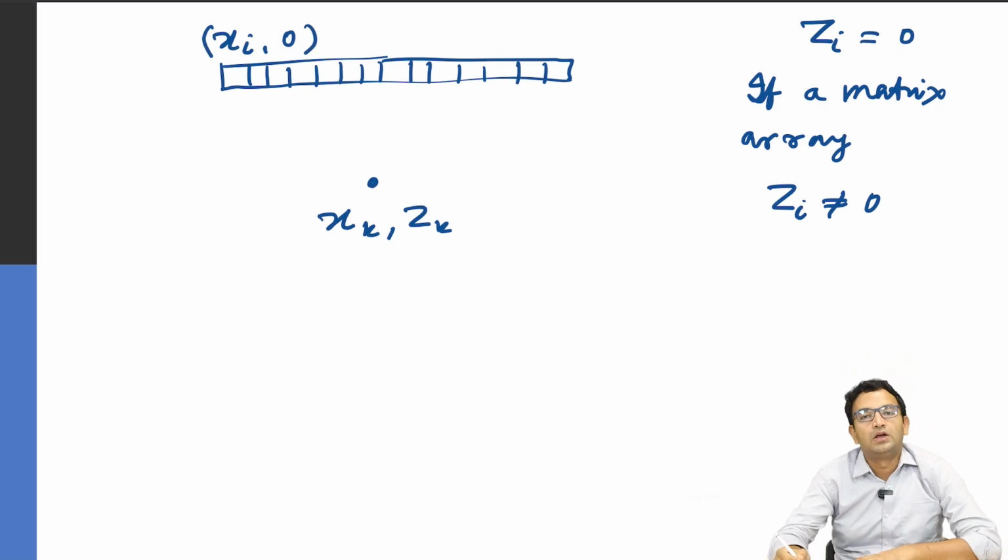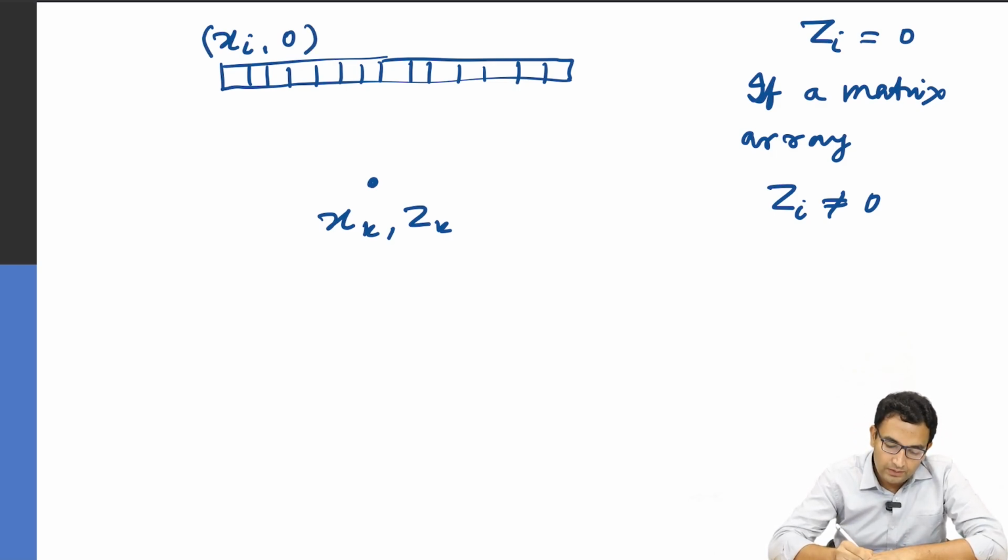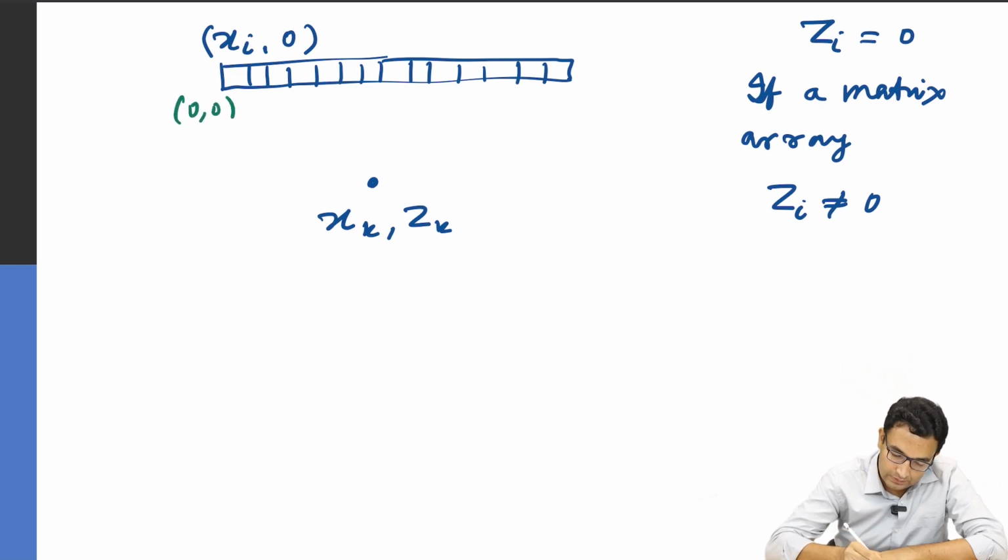Okay, so any particular element in the transducer, like for example here or here, can be represented by xi if I consider this as the origin 0, 0. Okay, so let me write that down here. This is the origin 0, 0. Now what's interesting is we know the pitch of the transducer, right? So we know the element to element distance. So we essentially know the distance.